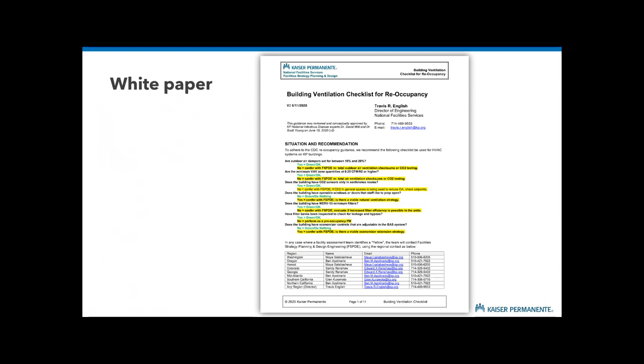Does the building have opening windows that you could prop open? No, so you're green. Do you have MERV 13 filters? Yes, then you're okay. If no, then you would call one of my engineers. Have your filters been inspected to check for leakage and bypass? Hopefully that's an annual PM for you, so you should be checking yes for this.